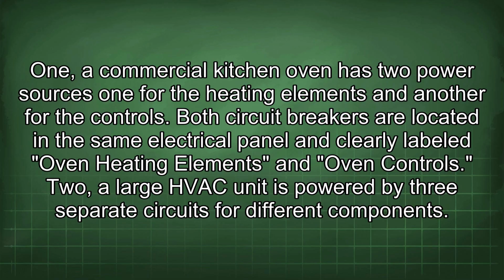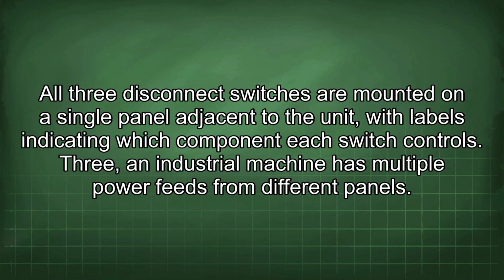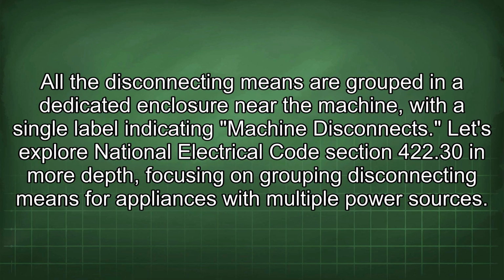2. A large HVAC unit is powered by three separate circuits for different components. All three disconnect switches are mounted on a single panel adjacent to the unit, with labels indicating which component each switch controls. 3. An industrial machine has multiple power feeds from different panels. All the disconnecting means are grouped in a dedicated enclosure near the machine, with a single label indicating machine disconnects.